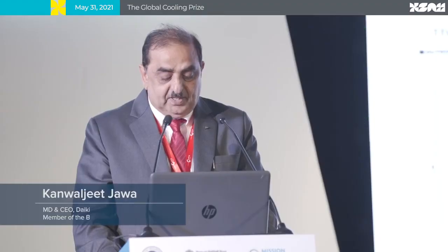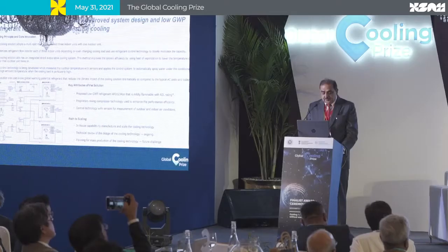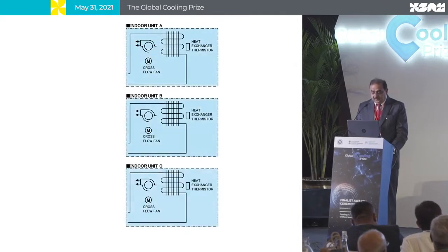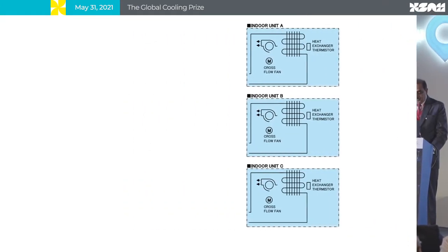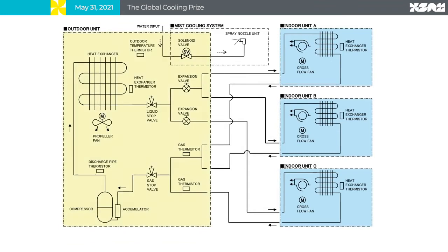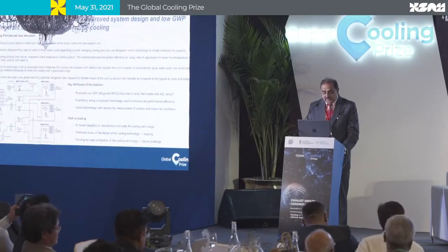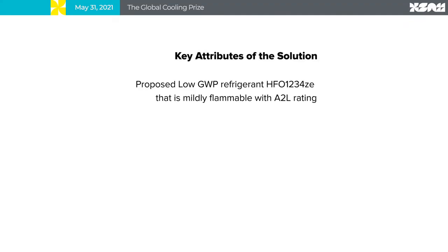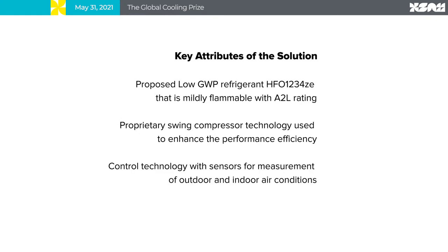Still lower, yeah. Firstly, we will adopt a multi-split method to connect 3 indoor units with 1 outdoor unit. This method optimizes refrigerant flow for each of the 3 units depending on ever-changing cooling load, using refrigerant control technology to closely modulate the latent heat and sensible heat capacity. Also, in this system, we are using an evaporative cooling method, which supplements energy efficiency and helped us achieve the score we reached in the Global Cooling Prize.